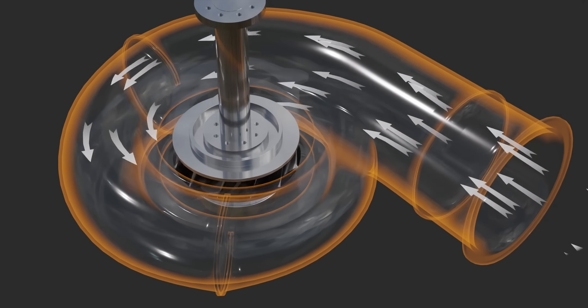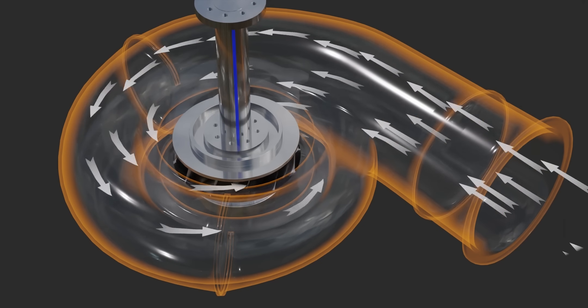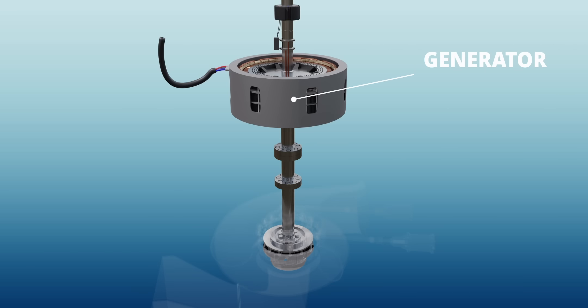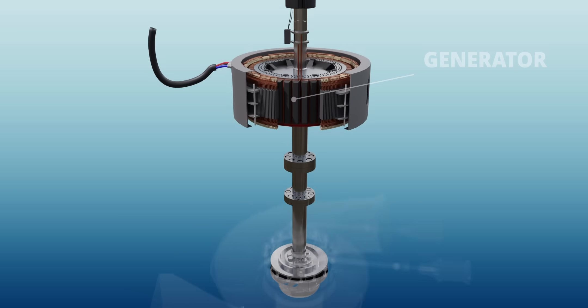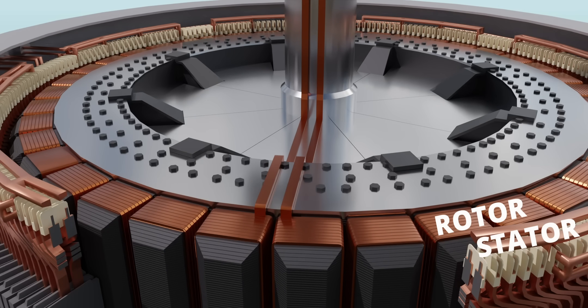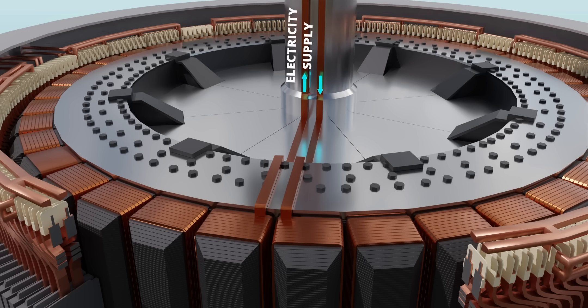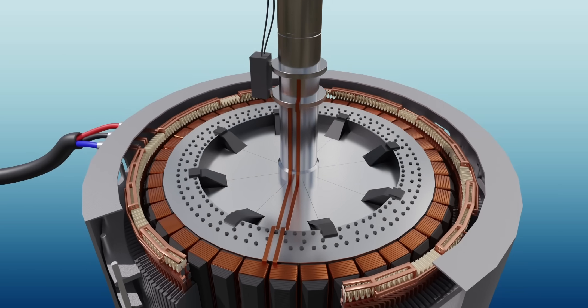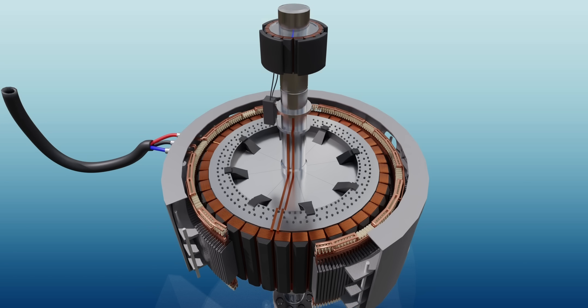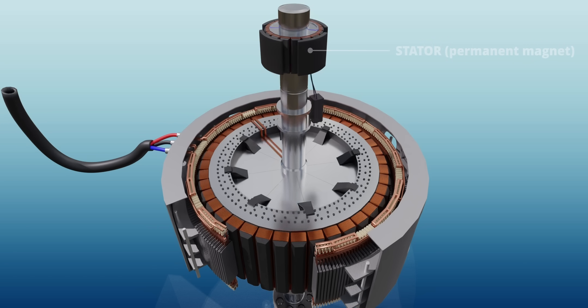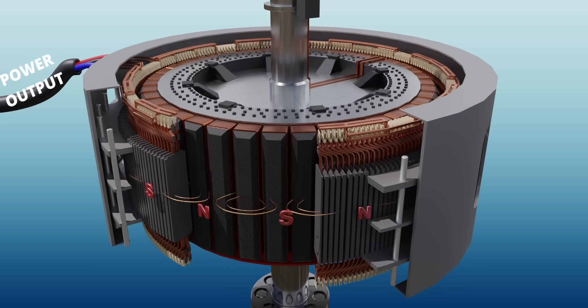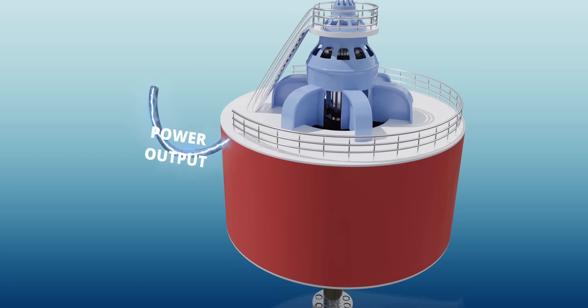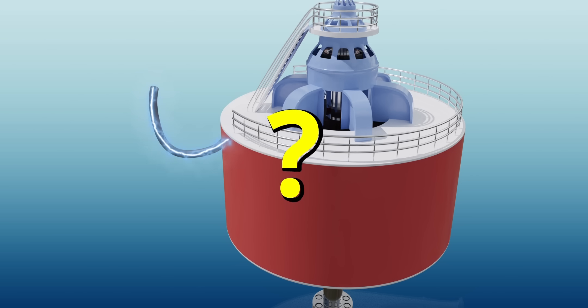The Hoover Dam uses a type of turbine called a Francis turbine. Water initially travels via a spiral casing and finally through the runner blades — the force of the water turns the runner. The runner is directly connected to the generator. Both the rotor and stator are just copper coils — no permanent magnets are used. However, the rotor needs a supply of electricity to generate magnetic fields; this current is supplied by an exciter which uses a permanent magnet stator. Now it's time to transmit this electric power.